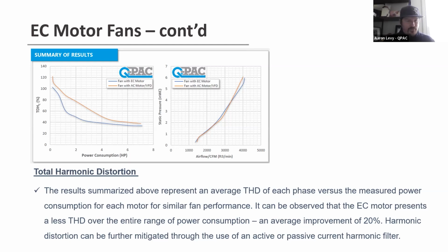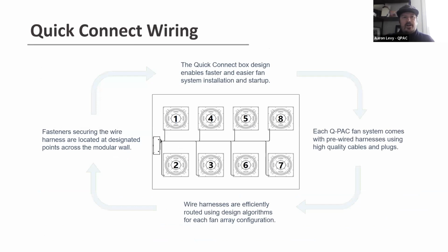Without using an active or a passive harmonic filter in line with it to bring it to less than 5%, which you would need for both. So in a lot of cases, I tell people, if you currently have a VFD system already on premises, going to an EC fan solution isn't going to make a big difference in the grand scheme of your harmonic distortion. A lot of places like hospitals or data centers, where it can be critical, already know they may need that just to eliminate it altogether, and they will buy an active filter to put in line. And we have partnerships with those that can help, that we can price into an application if need be. Like I said, with our quick connect wiring, it makes life a lot easier for the installer.